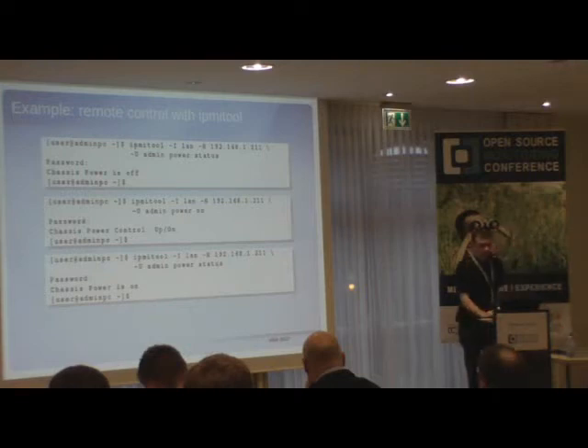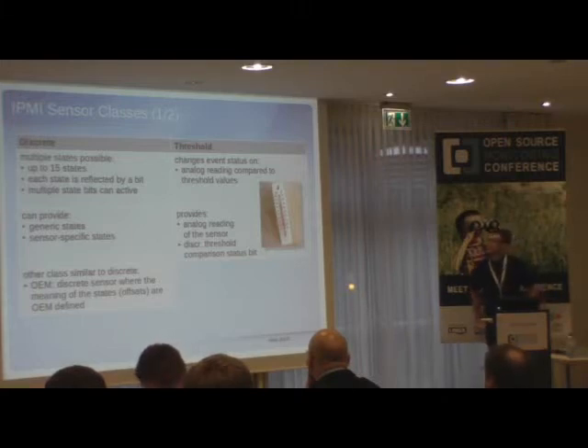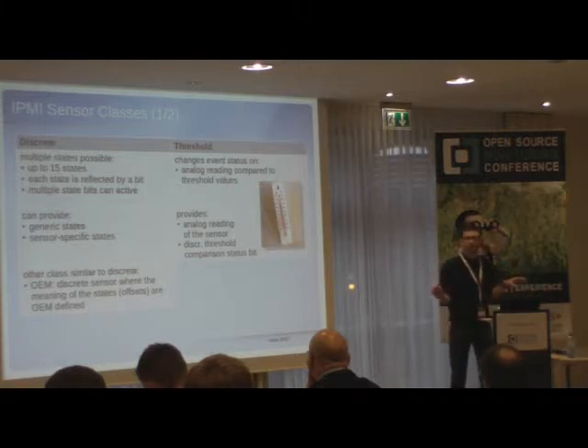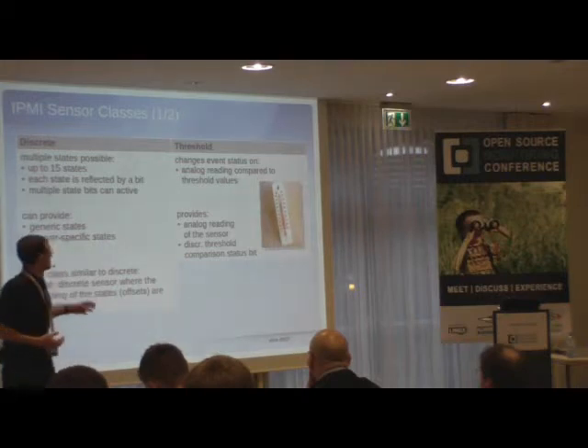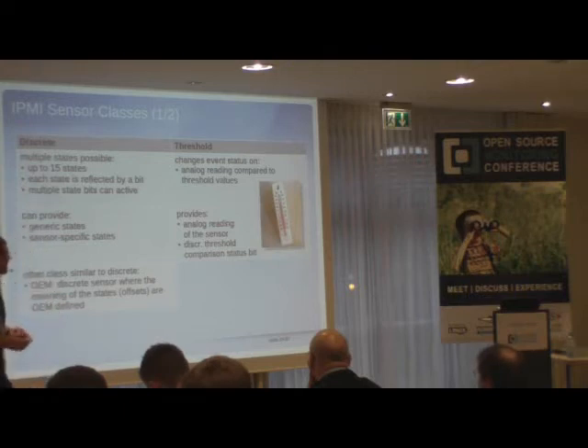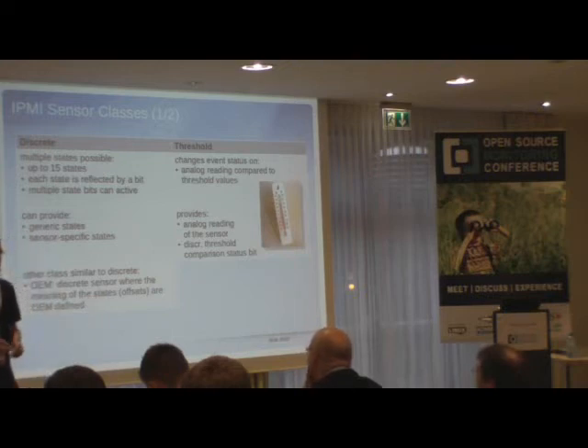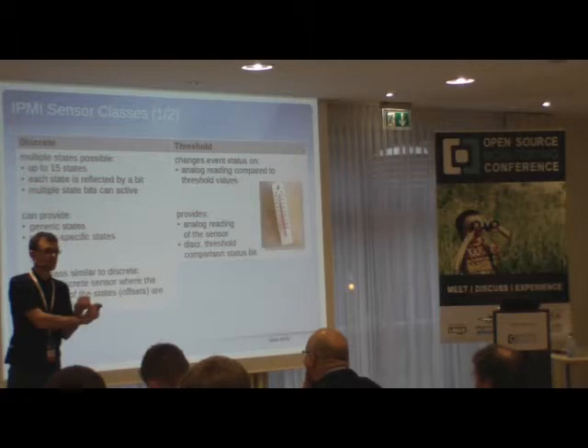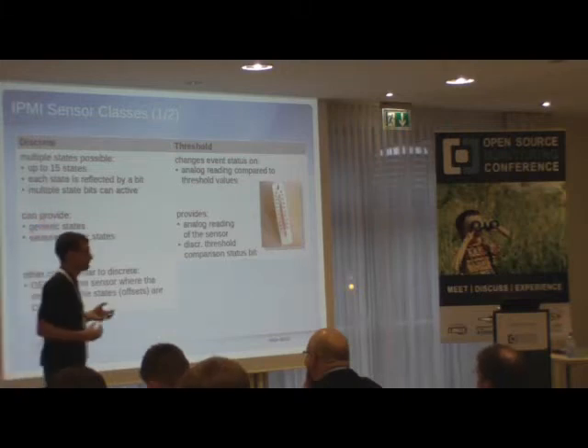When we talk about IPMI sensors, we come to a slide that looks a bit more complicated than before, but for good reason. There are two types of sensor classes within IPMI, which is very beneficial. On the left side are discrete sensors, which have the possibility to use up to 15 different yes/no states. For example, when you have a power supply, you don't get a numeric value — you get information like: the power supply is present, has power on the inlet, and is working correctly. So you have up to 15 different states available.